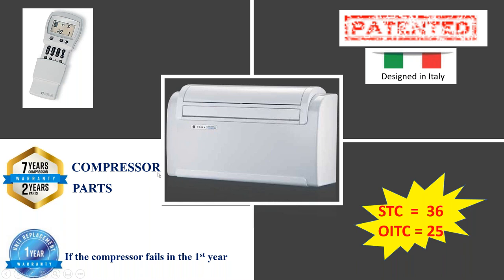The compressor has a 7-year compressor warranty. There are 2 years of warranty on all parts, but if a compressor fails in the first year, you get an entirely new unit. The only thing that we would ask is that the unit that has a failed compressor be returned to me or be returned to a local service center that we would designate. And a service center would essentially be, in Italy they're called service centers, in the US they're called contractors, right? Or dealers. So if you have dealers in mind or contractors in mind that you think would serve well, we can qualify them as a service center and then call them an authorized Olympia Splendid service center. Because any unit that fails, we want to know why.